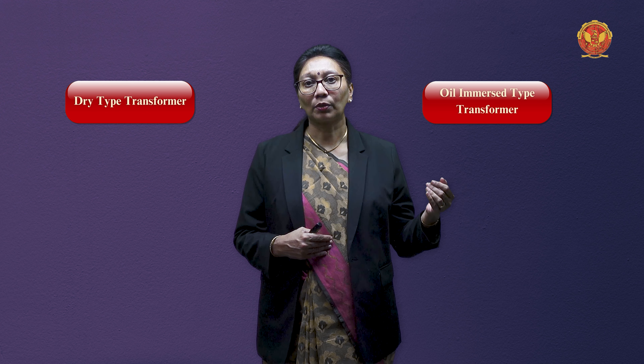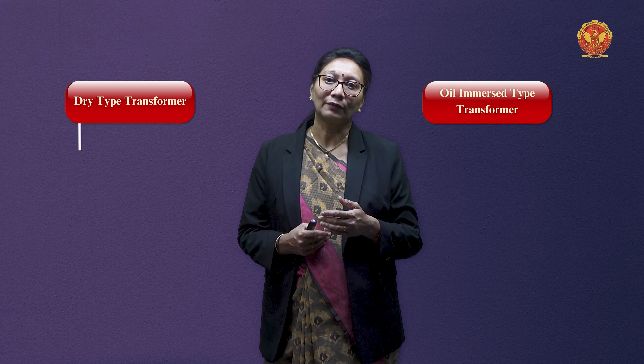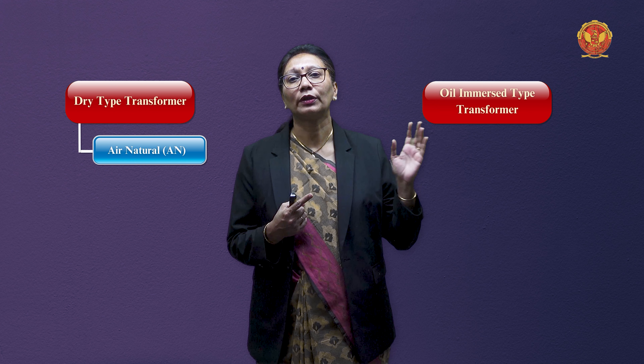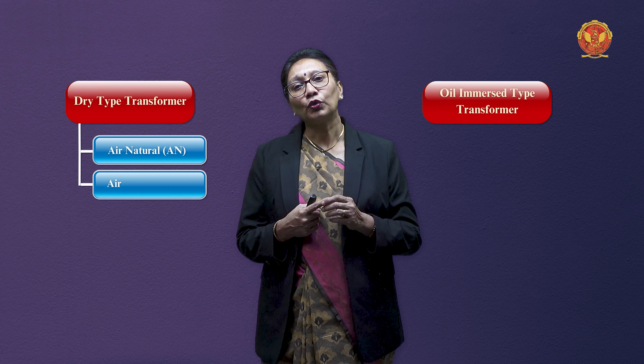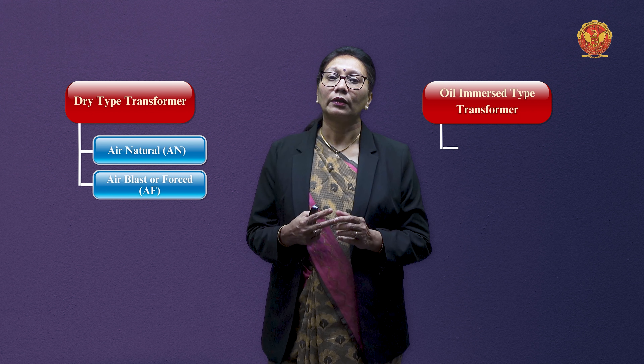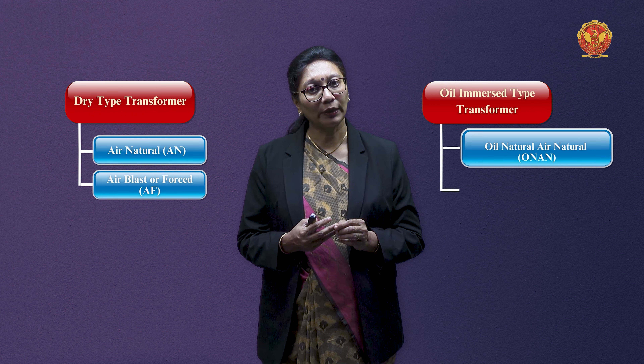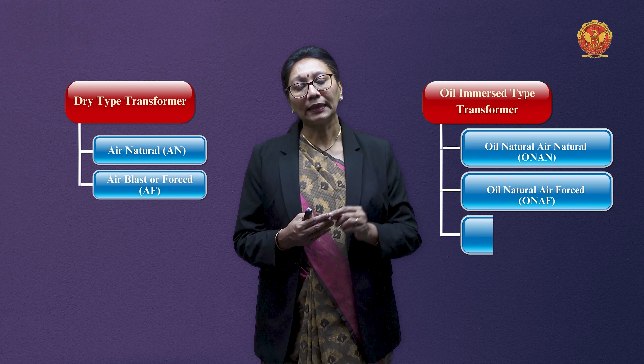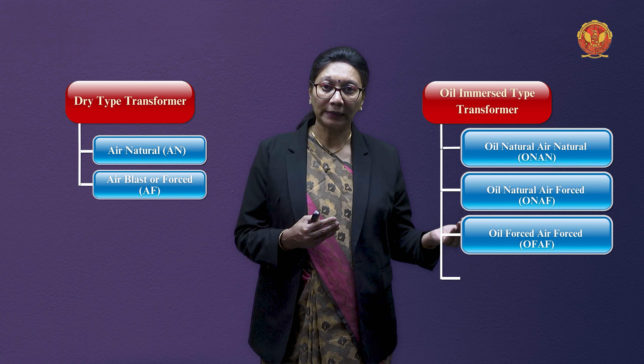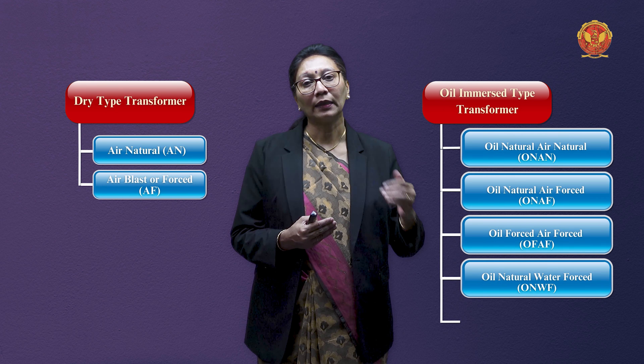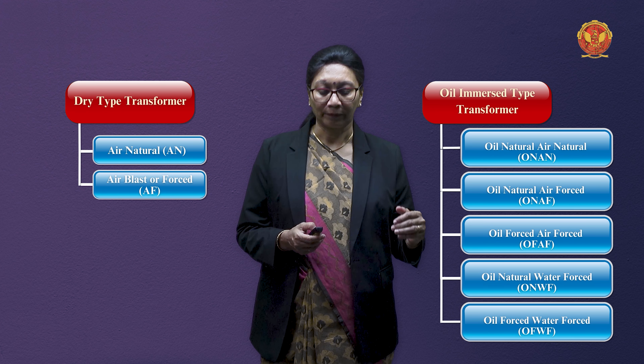Basically there are two types of transformers: one is dry type, in which no oil or water is used, and the other is oil-immersed type. For cooling of transformers, the major common methods are: air natural, air blast and forced, oil natural air natural, oil natural air forced, oil forced air forced, oil natural water forced, and oil forced water forced cooling.